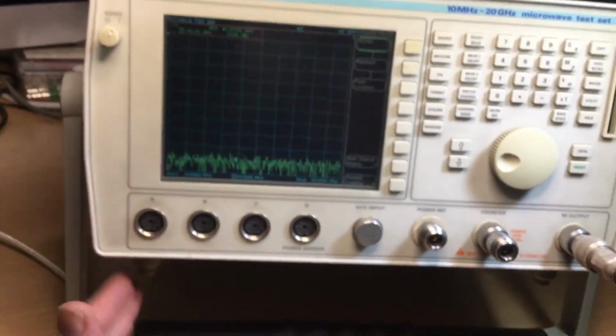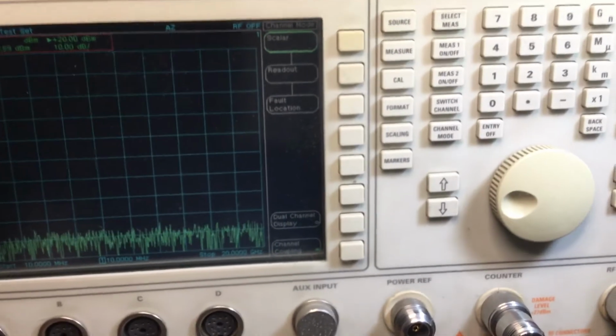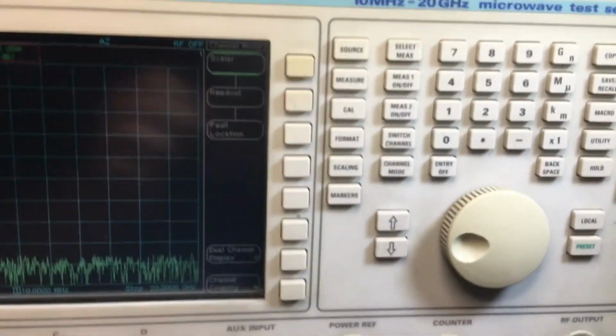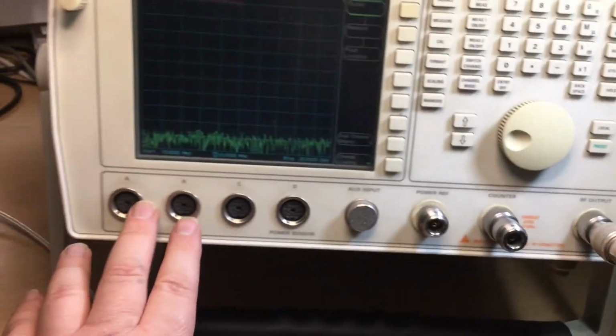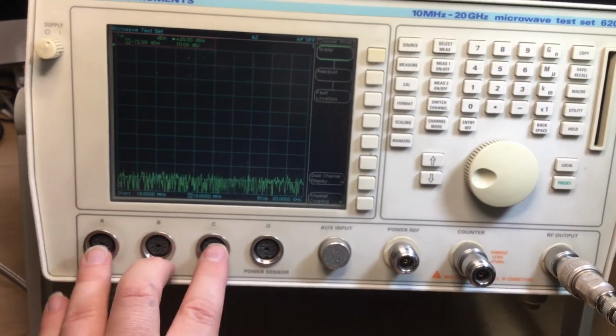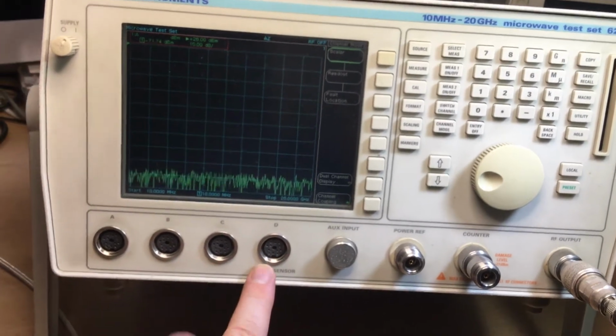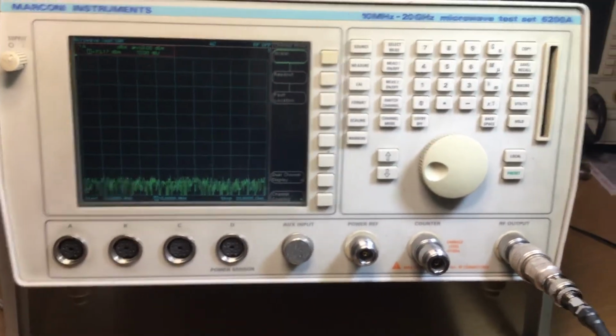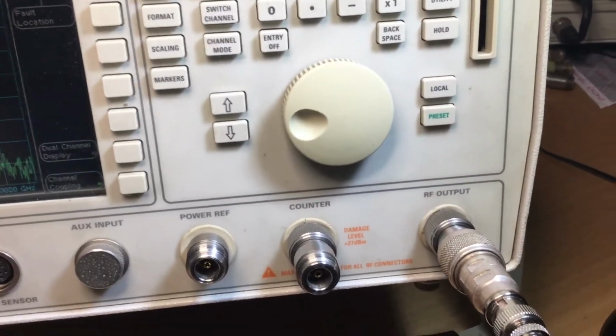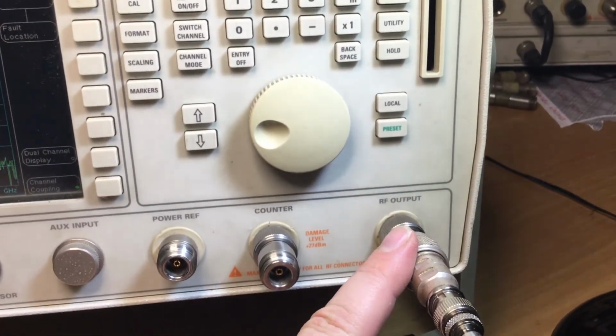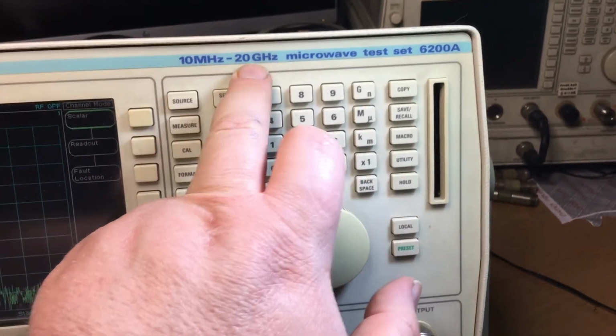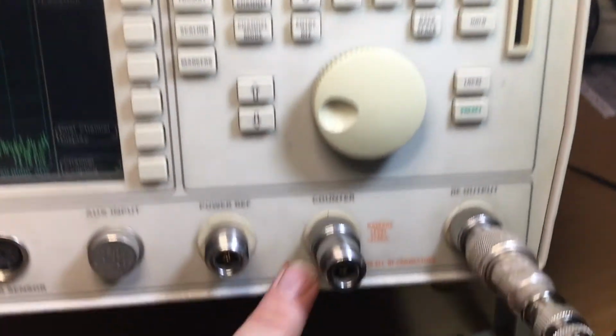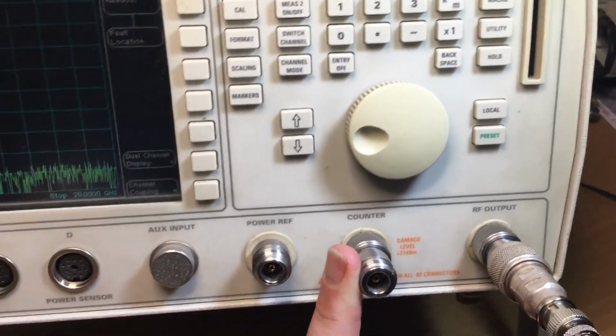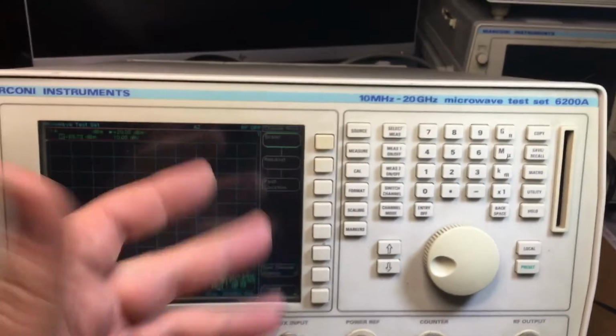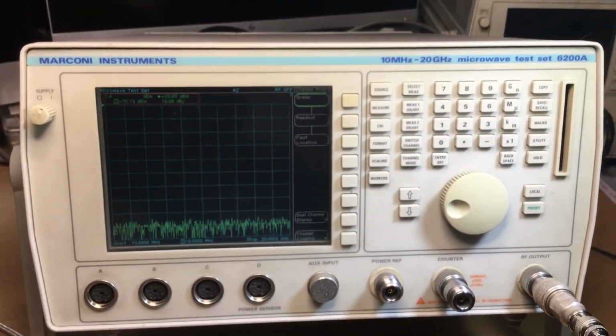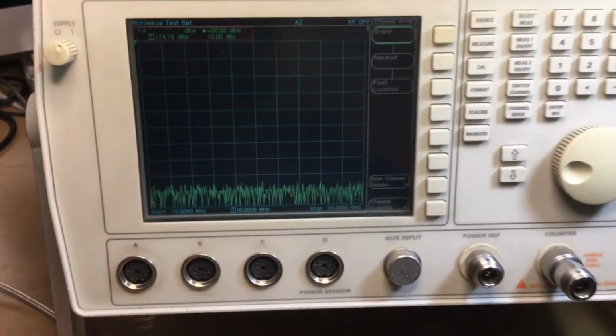Now the nice thing about it is a lot of these test sets are available quite cheaply. Even if you don't get the sensor probes, the scalar probes and the power sensor probes, they do come up quite often on auction sites. And because you've got an RF generator from 10 MHz to 20 GHz, and also a frequency counter from 10 MHz to 20 GHz, these test sets often retail now at around the £500 mark to £1,000, depending on what you get with it.